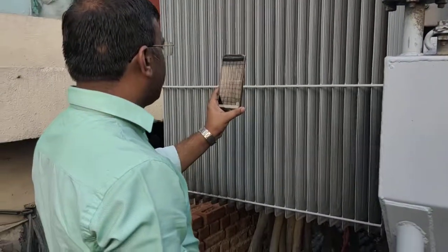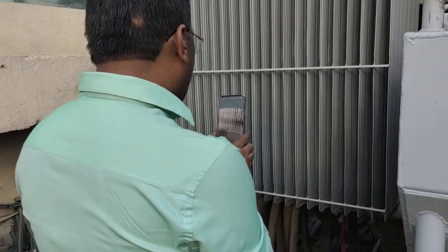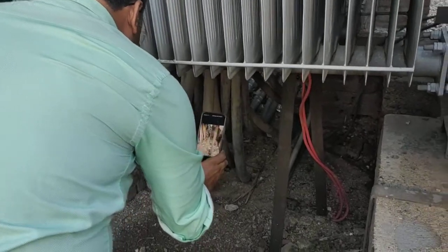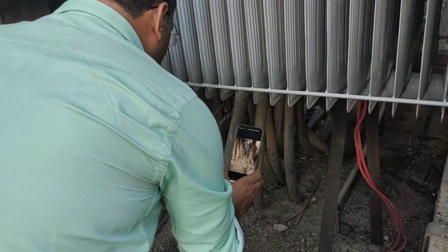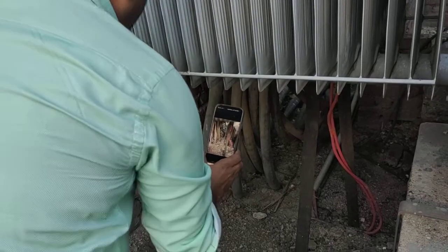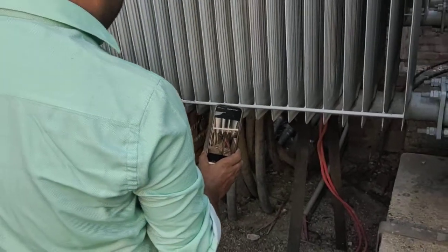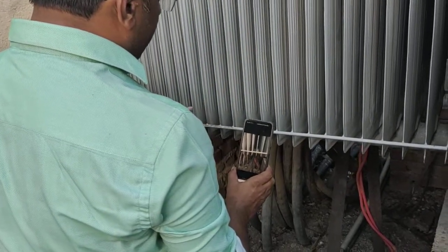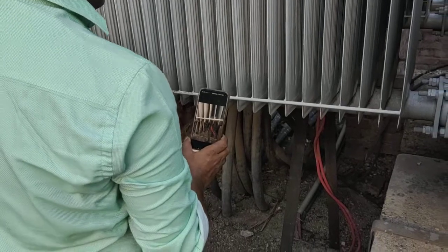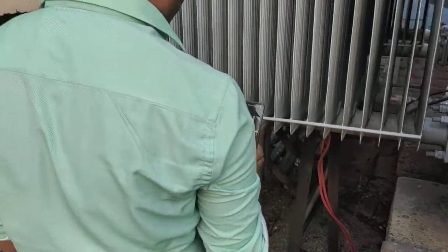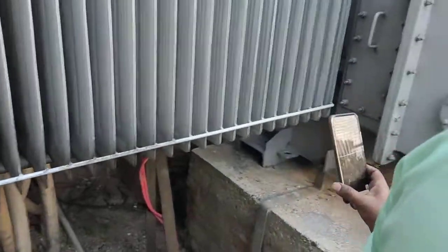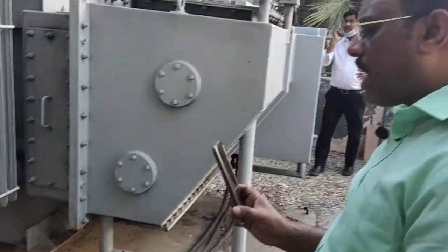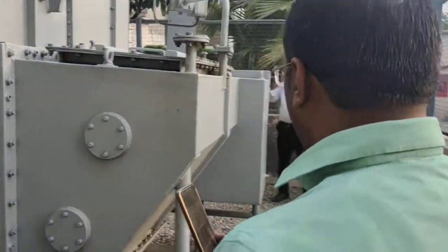I'll show you the earth tester. Once you are doing the earth testing, one of your points should be attached to this. The second point will be attached at a distance of around 1 meter, and then you do the measuring. If the value shows 0.5, 0.6, 0.7, and it is under 1 ohm, then it's okay. If it is increasing, then you need to recheck your earthing. You can add bentonite powder or any chemicals, such as charcoal, versus the normal conventional method. We are using charcoal and salt.